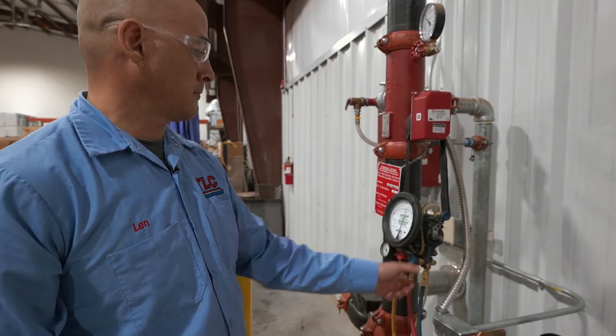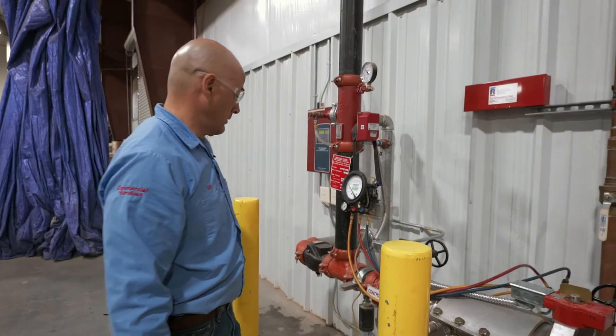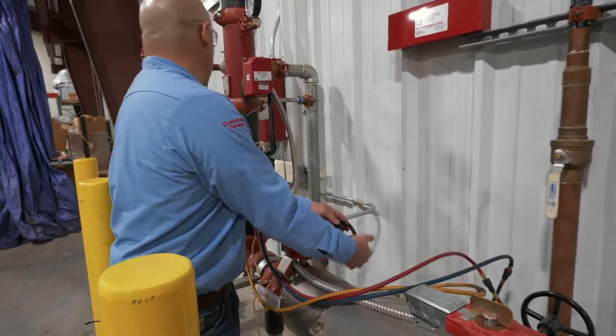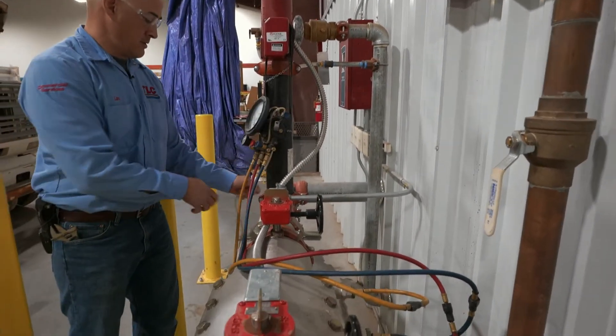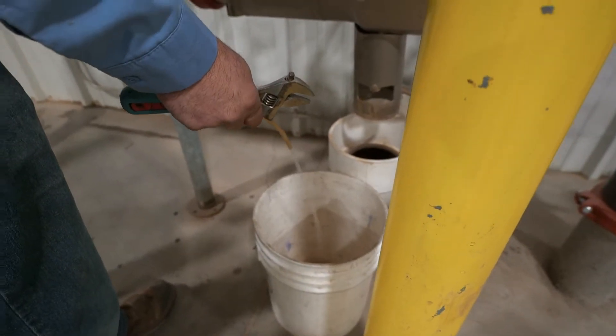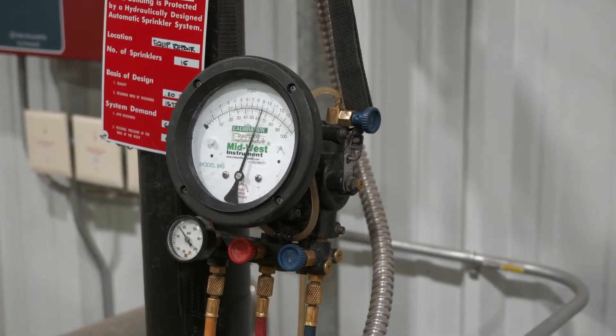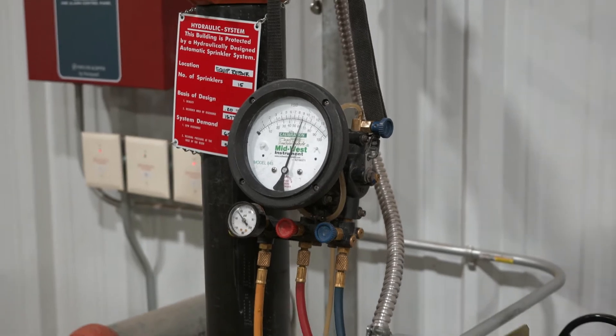For a fire suppression system like this, we need to do the following. The first thing we do is shut the water off. Water is shut. So this would be test number one — we're testing check valve number one. It's got to be at a minimum of five pounds. It's reading 9.4 pounds, so that would be good.